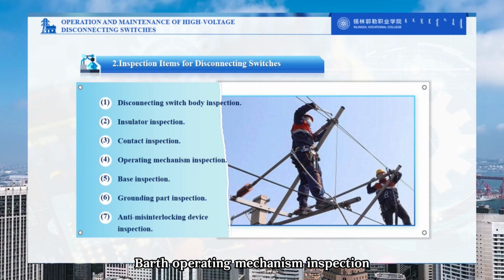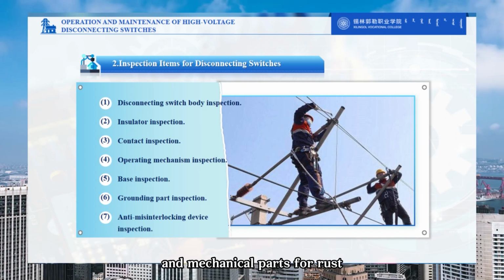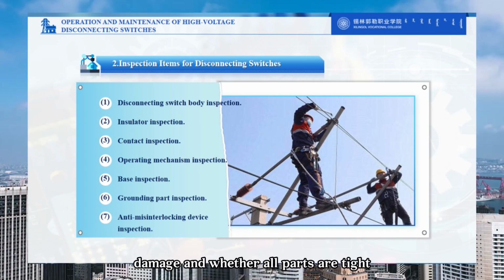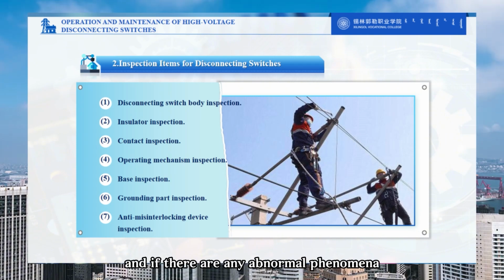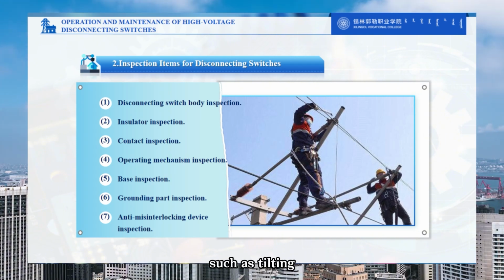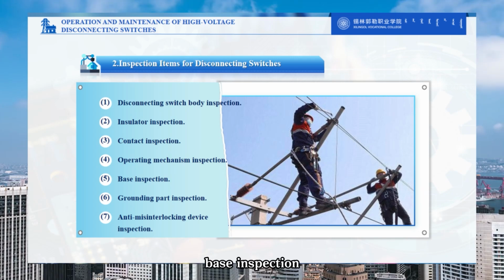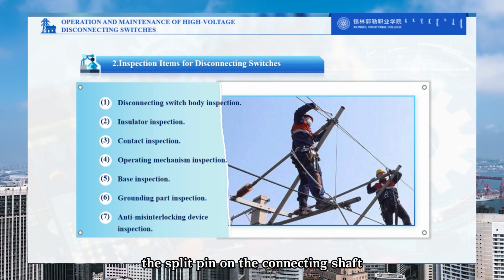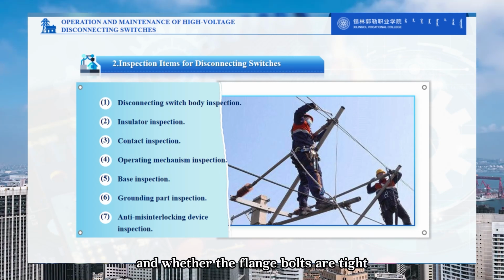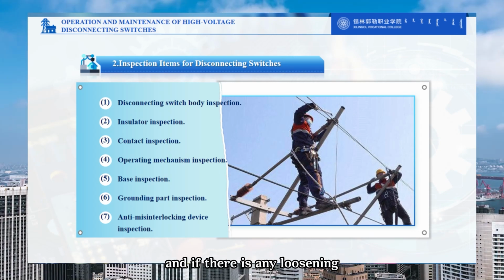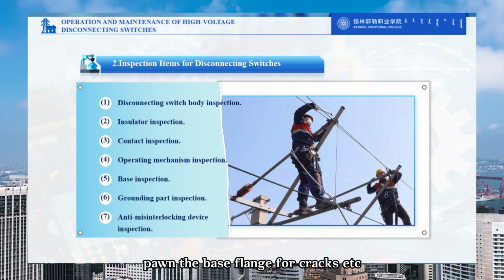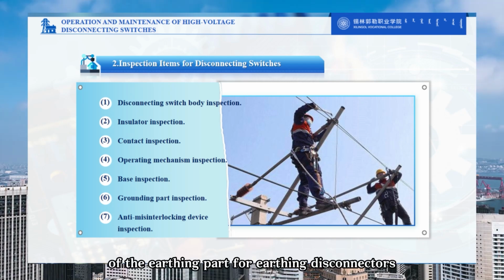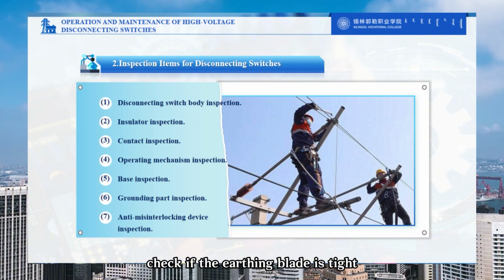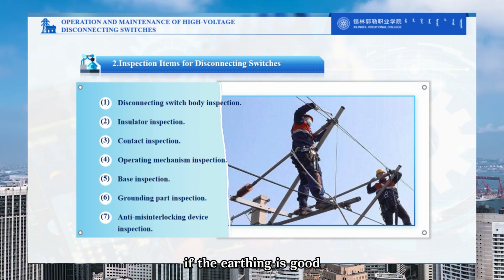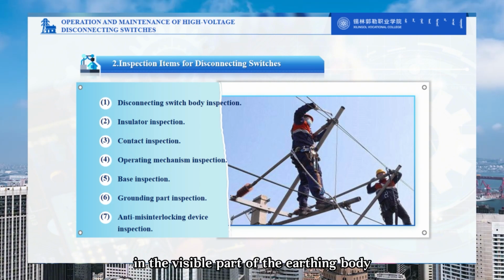Fourth, operating mechanism inspection. Check the operating linkage and mechanical parts for rust damage and whether all parts are tight, and if there are any abnormal phenomena such as tilting, loosening, or falling off. Fifth, base inspection. Check the disconnector base, the split pin on the connecting shaft, to see if it is broken or fallen off, and whether the flange bolts are tight and if there is any loosening. Check the base flange for cracks, etc. Sixth, inspection of the earthing part. For earthing disconnectors, check if the earthing blade is tight, if the earthing is good, and if there are any breaks in the visible part of the earthing body.